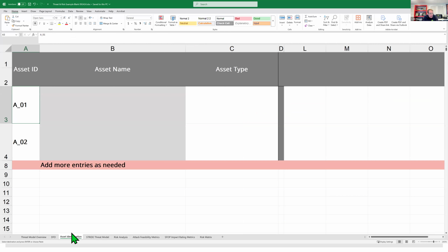We also considered IEC 81001-5-1. That's the Secure Product Development Framework process that we follow. And also SW96, which Milton mentioned, which is a risk management process. Both that and 81001-5-1 are recognized FDA consensus standards. So we really work to make sure that this spreadsheet and the process that I'm going to show you here today meets FDA expectations. The FDA doesn't map this out in this sort of detail, so we kind of had to connect the dots ourselves.